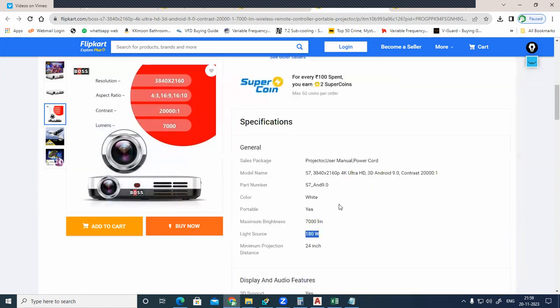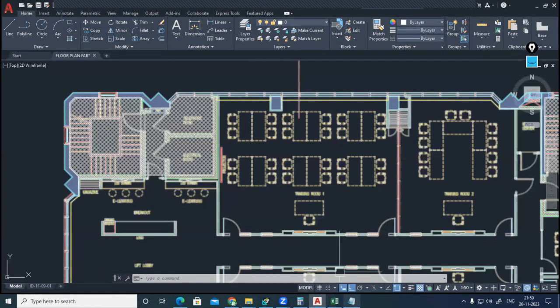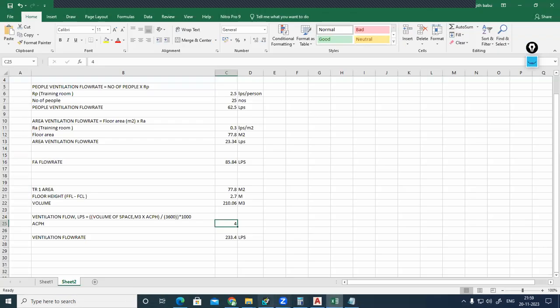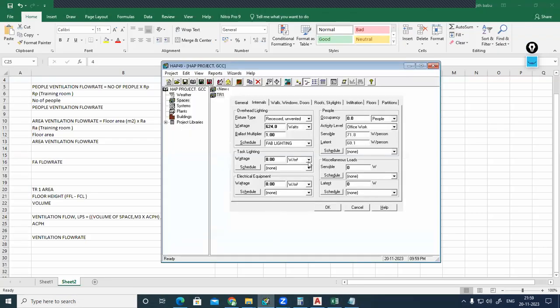That's why, since the equipment is fully located within training room one, for the rated load you should consider 100% of heat gain. But that is unpredictable. We don't know the manufacturer. For safety, I'll consider a maximum of 300 to 500 watts. So let me consider, instead of watts per meter square, watts, 300 watts scheduled.